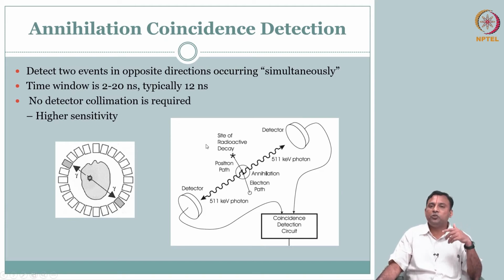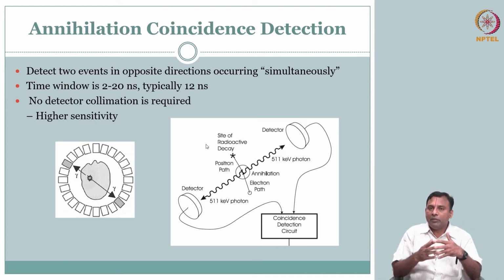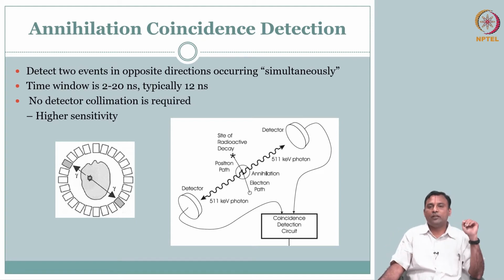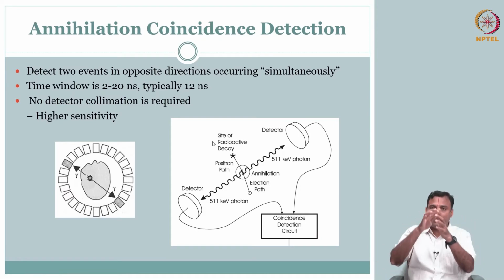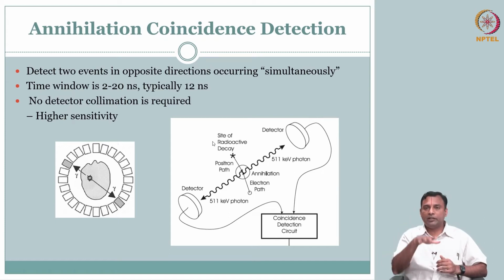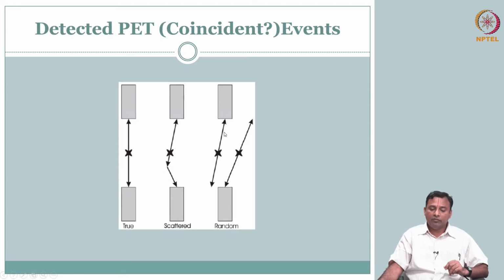So I don't need to really use, say we talked about sodium iodide with thallium, a generic one that can be ready for different radio tracers. I can actually get something very fine tuned and efficient for your 511 kilo electron volt. And therefore the detector here is slightly different. Instead of using just the Anger camera with one crystal, the big head that you saw, here we could do a little better because of the known requirement.